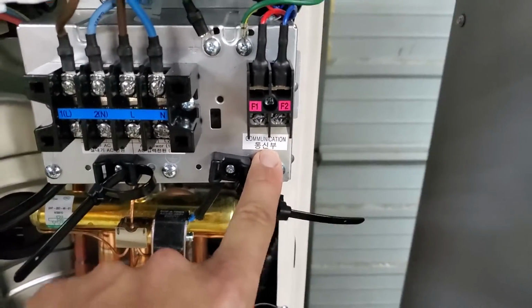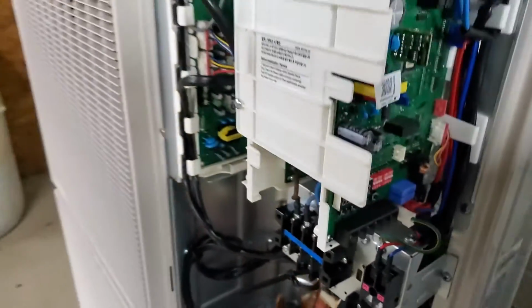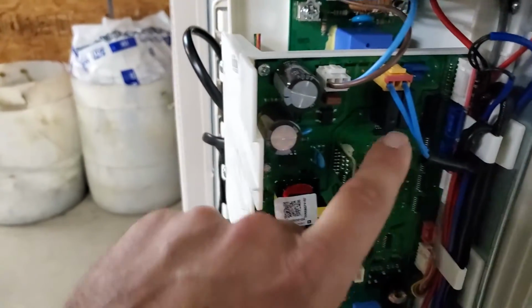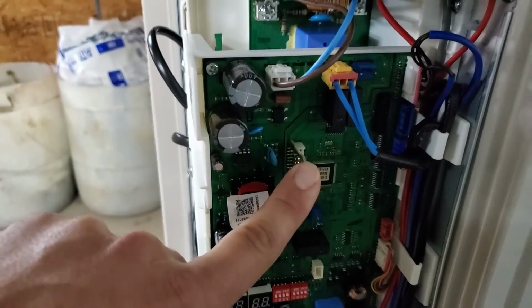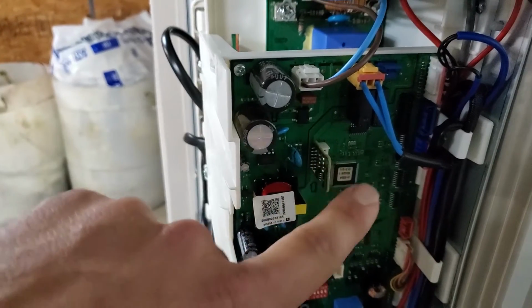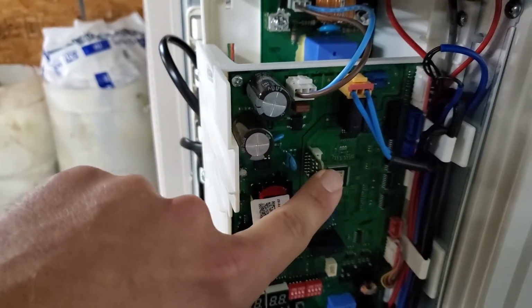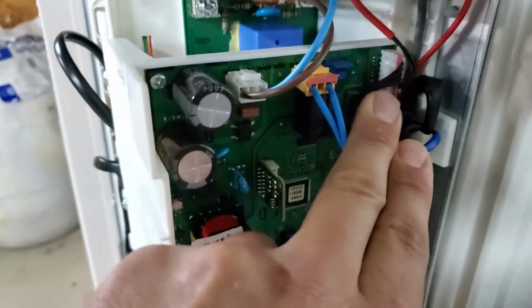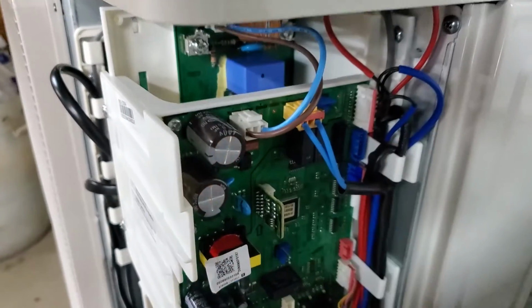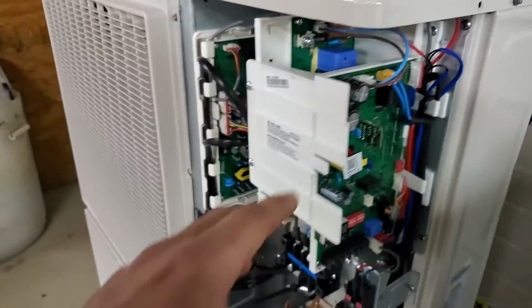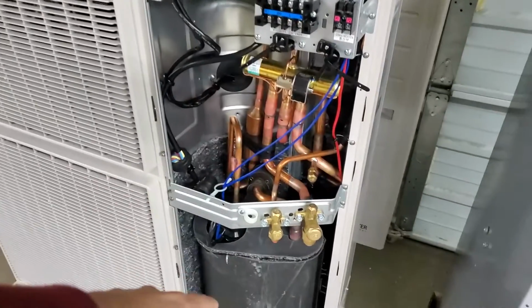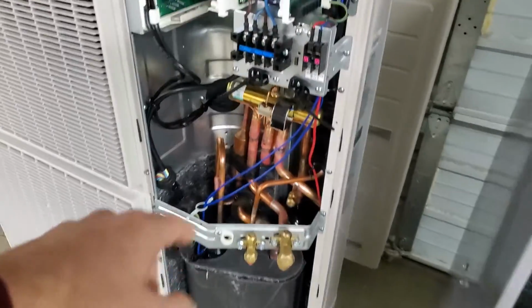This is the F1 and F2, which is your communication. We'll look at the indoor unit here in a minute. I want to talk about the EEPROM. The EEPROM is your removable data here. This is a removable EEPROM, stores all your data. You've got your overload protection. You have logic that protects your compressor. Built in, you have the ability to maintain your discharge temperature. You have overload protection for your compressor.